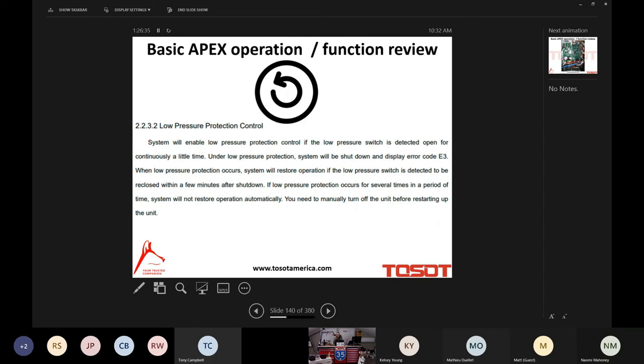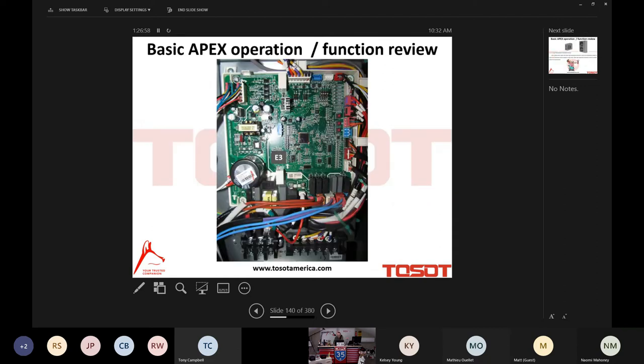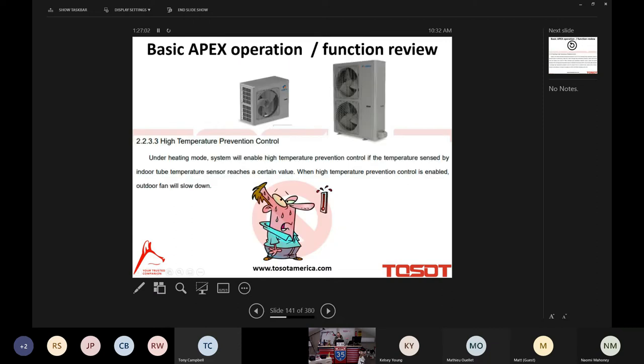Same thing with low pressure control. The same thing happens here. Instead of high pressure, low pressure now. Low pressure, we can speed up the compressor to try and compensate for that. Eventually, it won't be able to. I mean, in a low pressure situation, you probably got a leak, and at some point, no compressor is going to be able to compensate for that, and it's going to throw you the E3 error. And then you can see the E3 error being displayed at the outdoor unit.